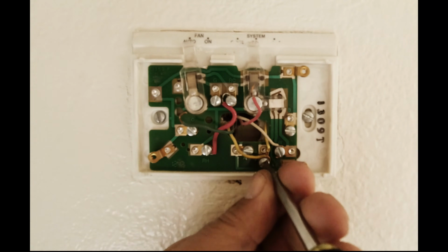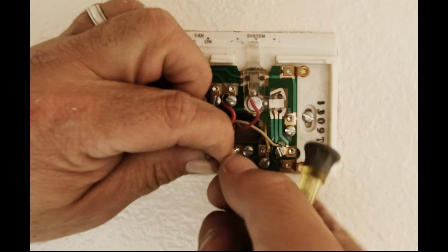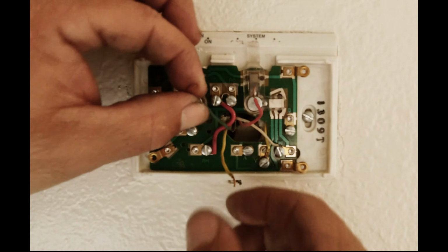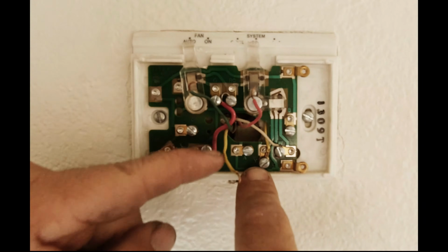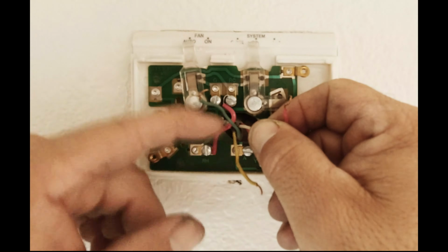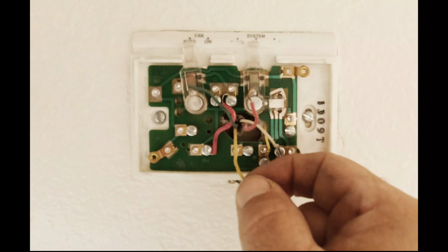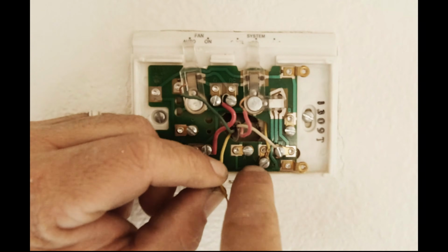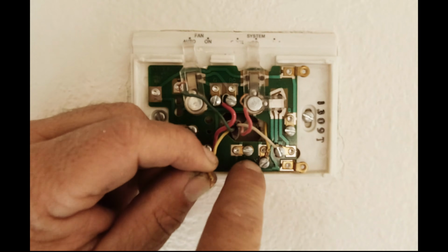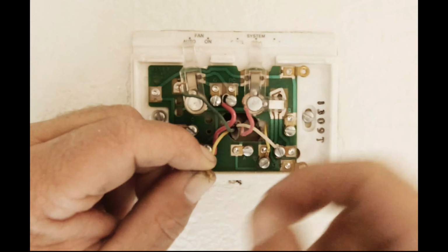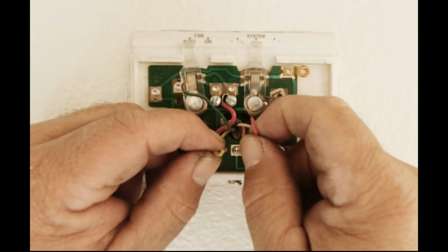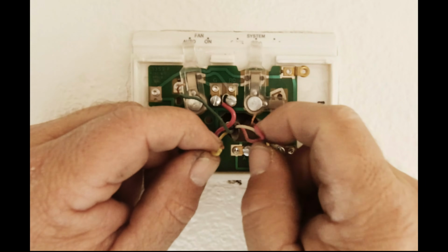Now, the yellow is always going to be the compressor. Whatever's connected to the Y, that's going to be the compressor. And I say whatever's connected to the Y because the wires can actually change. If a wire went bad and the technician had to use another wire color, or sometimes they buy a cable with 8 wires and one went bad and they just switched to another. But whatever's connected to the Y, usually it's the yellow, but if it's not the yellow, that's going to be the compressor. Once you connect your 24 volts over to the Y, that should make your compressor kick in.